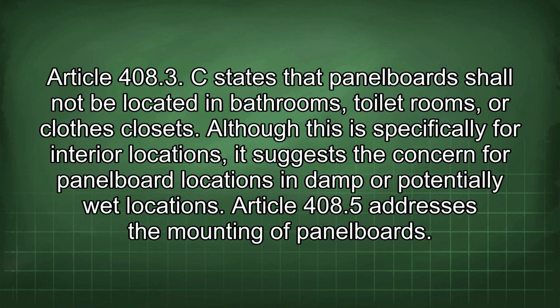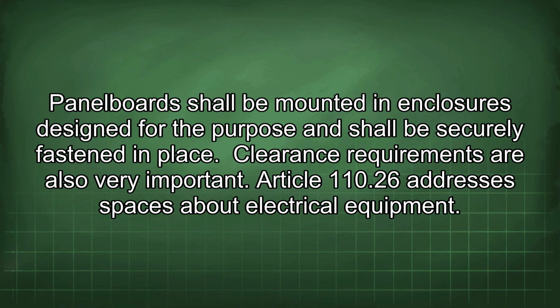Article 408.3 C states that panel boards shall not be located in bathrooms, toilet rooms, or clothes closets. Although this is specifically for interior locations, it suggests a concern for panel board locations in damp or potentially wet locations. Article 408.5 addresses the mounting of panel boards. Panel boards shall be mounted in enclosures designed for the purpose and shall be securely fastened in place.